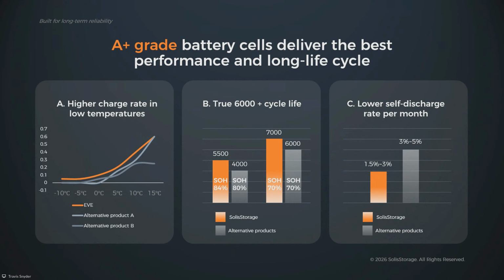And then we get better cycles. SOH is state of health. That's 84% at 5,500 cycles, and 70% SOH at 7,000 cycles. So you're around 19-20 years of cycles, if you cycle every day. If you're not cycling every day, you could potentially get 25-26 years out of the battery. When you go really below 70% SOH, balancing the cells becomes very difficult for any BMS to handle, so we really can't calculate what happens after that. That's why all the warranty documents are based around that 70% point - some even put 80% - because below it, it's very hard to say how long it will last.